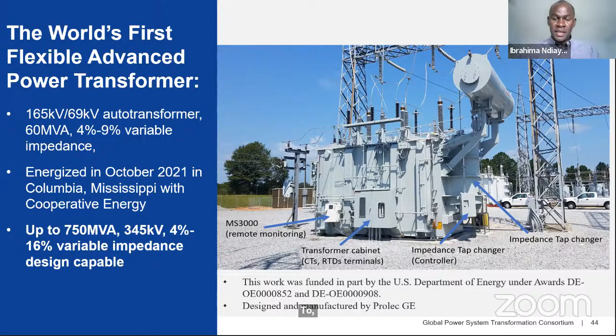Other than that, it has all the features and the same components, the same hardware, the same material as used today in a conventional transformer. It doesn't involve any power electronics. So obviously, the reliability was very important to us because of how critical transformers are. So we are using only known and compatible material to design and manufacture this flexible transformer. If you go to the next slide, please, we have a use case showing how it did operate on the grid.